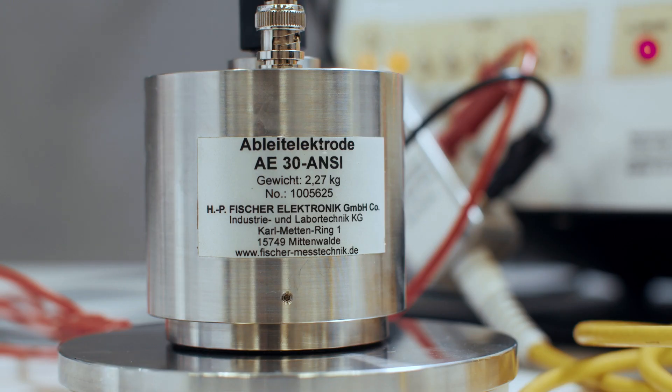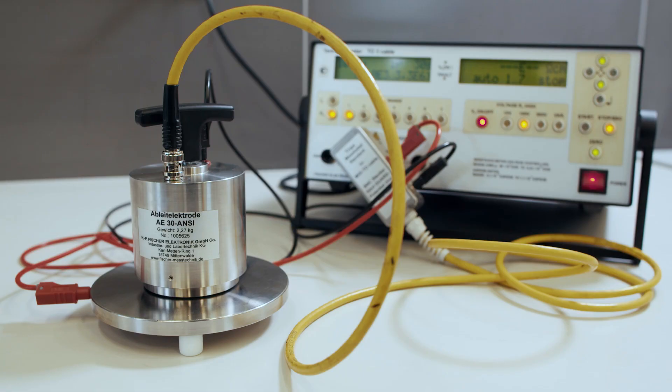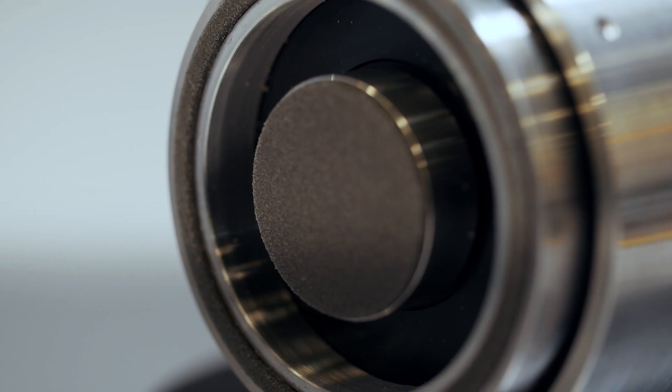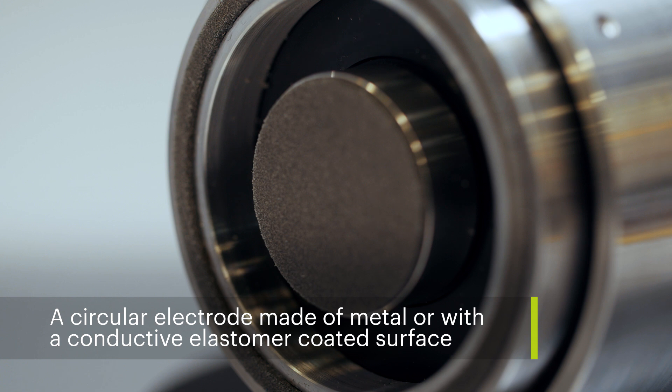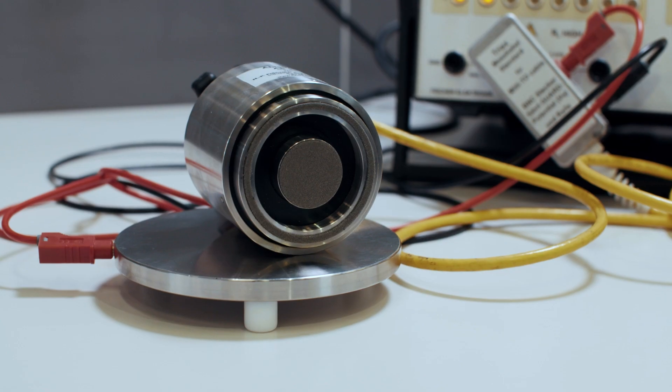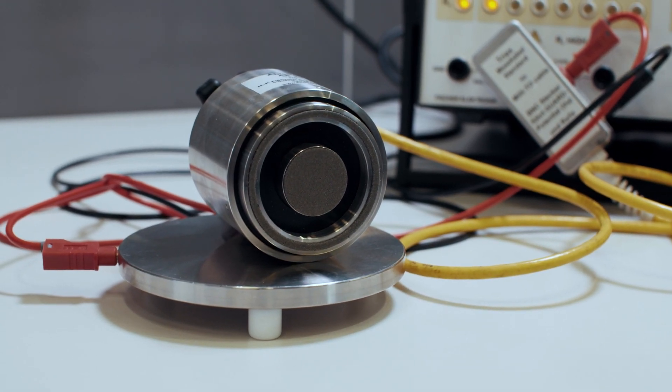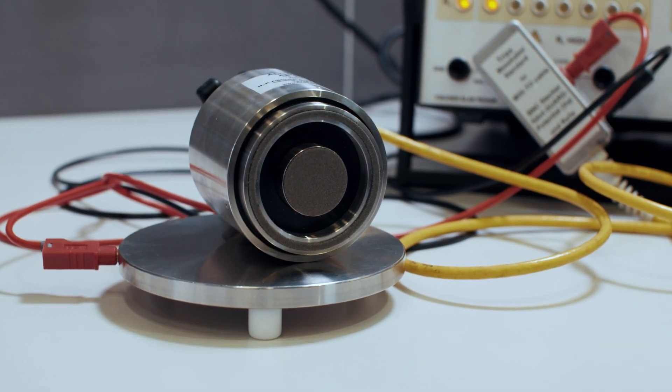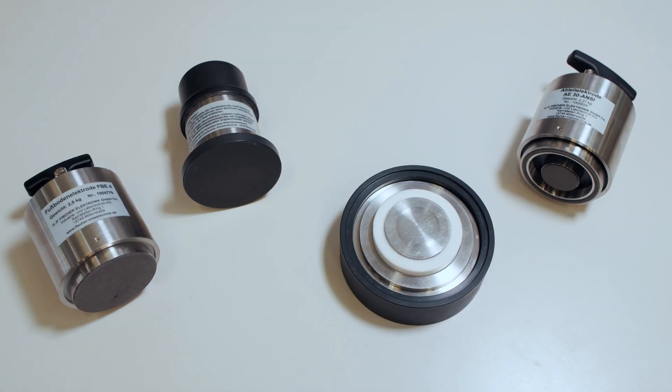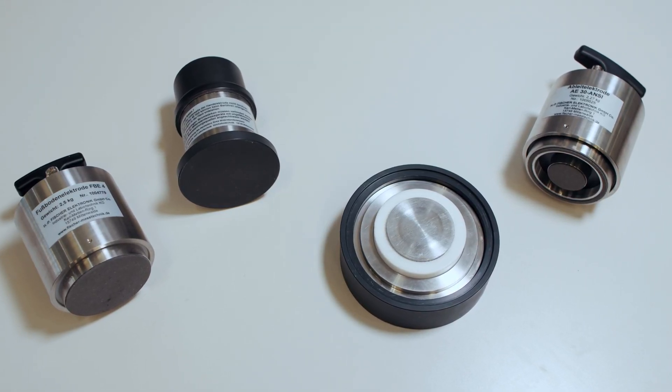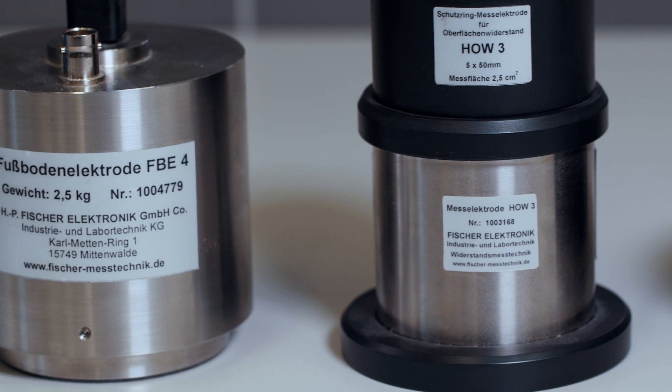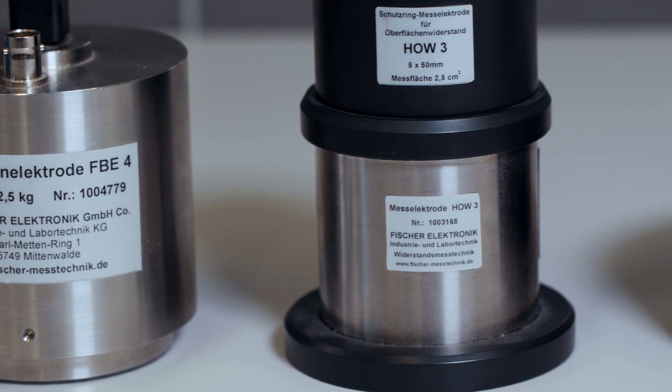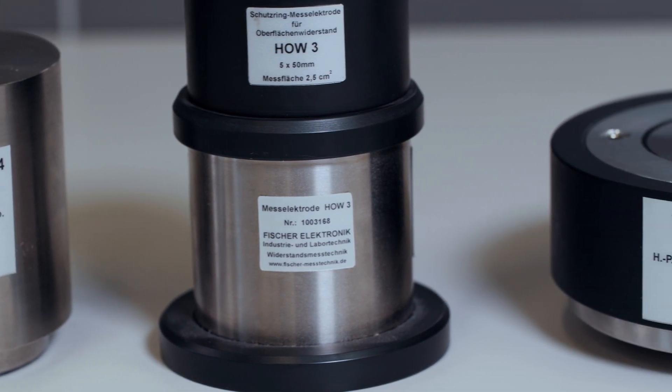When using the 2 probe method, there are several methods to reduce contact resistance. The use of heavy electrodes of more than one kilogram each and of conductive elastomer on the surface of the standard electrodes can minimize this effect. Special electrodes that are used in these standard measurement techniques also allow this to be reduced. However, none of these methods will eliminate it completely. It is simply impossible.